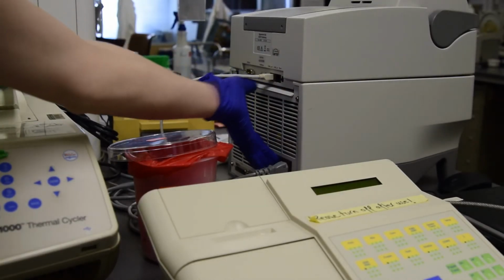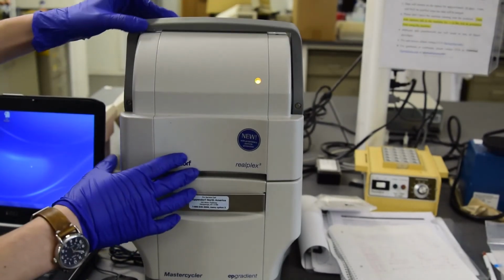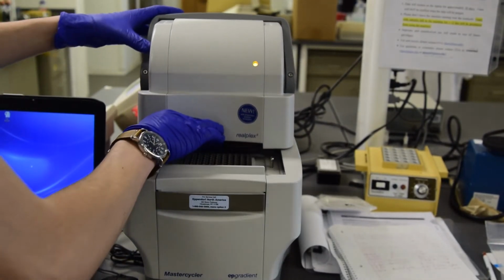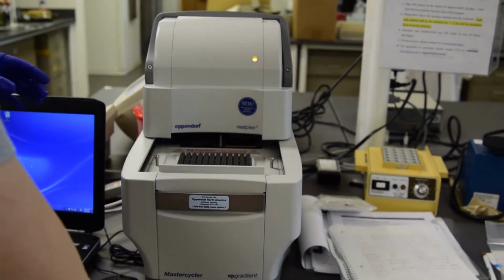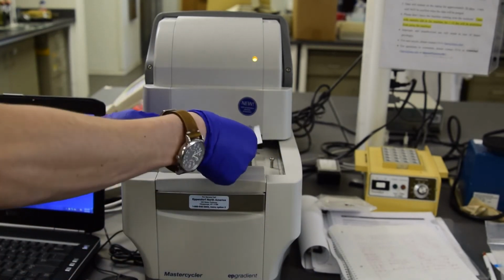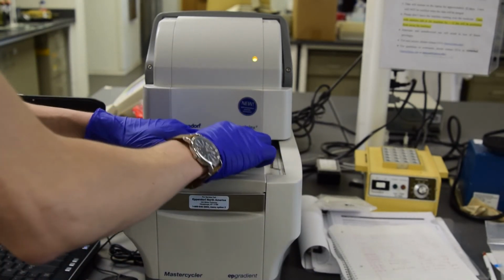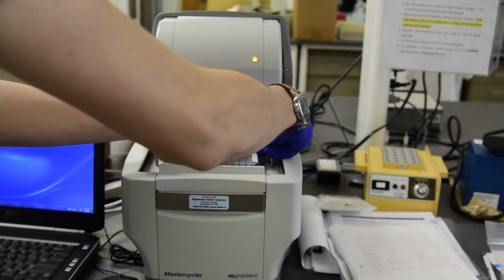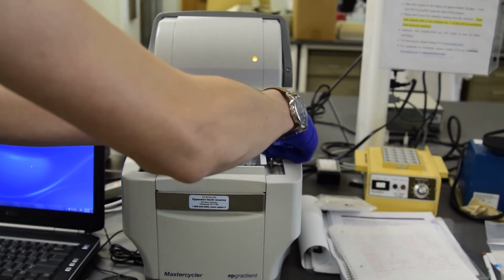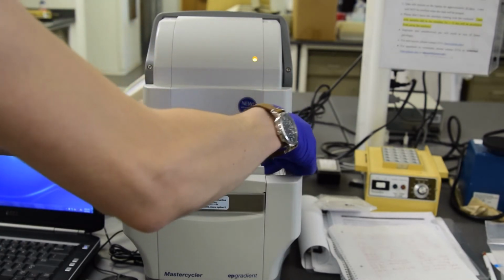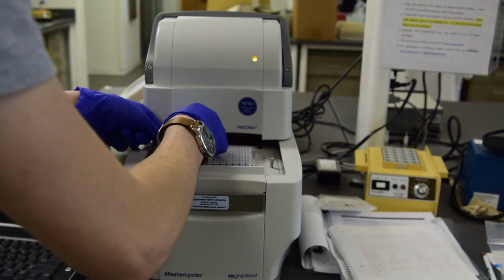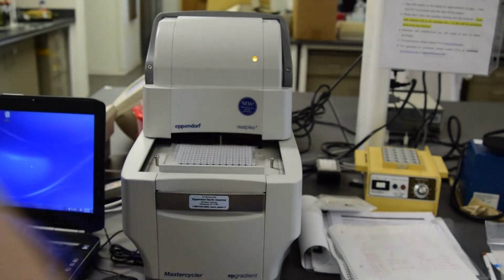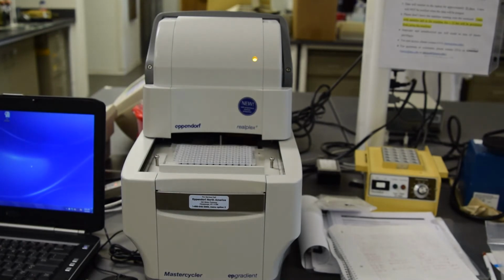Turn on the qPCR machine using the switch on the back. You will need permission to operate this machine once trained. Move the arm up, then push back the head of the machine gently. Place your plate in the wells with row A furthest from you. Remove the side tabs from the film. Seal using the roller in the drawer under the table on which the machine rests. Close the machine and push the arm down.